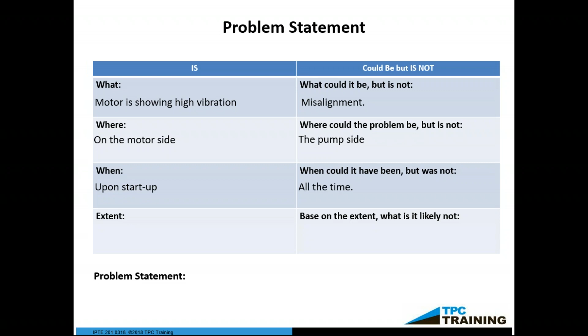Motor showing high vibration, could be misalignment. Where? On the motor side. On the pump side it could be, but it is not the pump side -- so we know it's the motor side. When does it happen? Upon startup. When could it? It could be all during the whole time it's running. The extent: there's a long history of vibration and wearing out bearings, and the shims are rusted out. That's probably not an issue with the pump, it's always the motor. So that's how you do a root cause analysis.